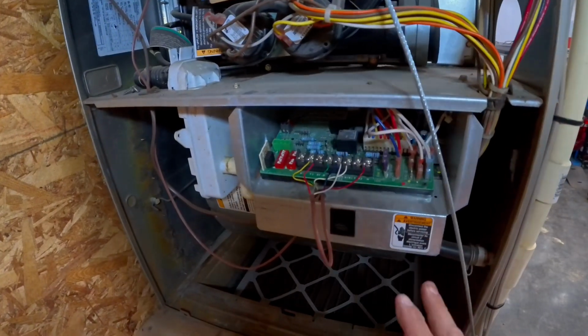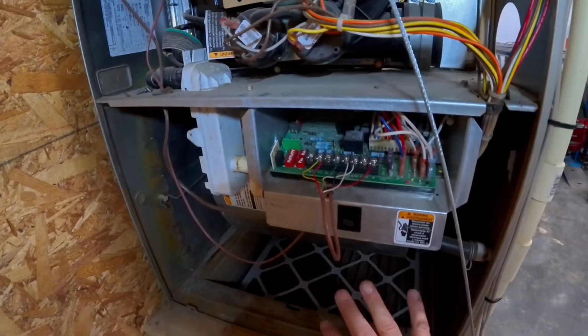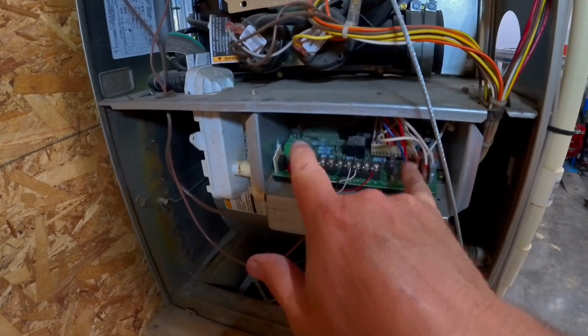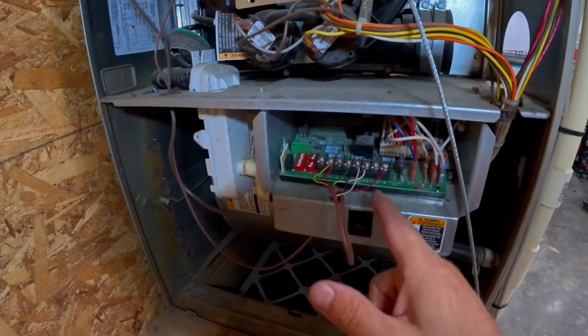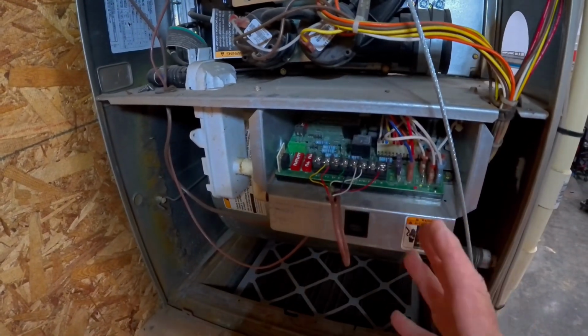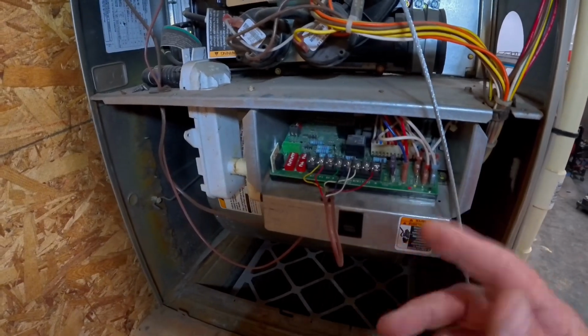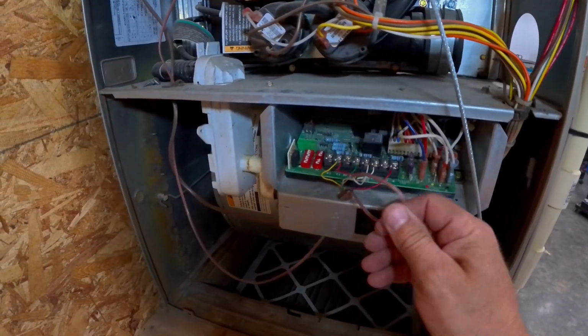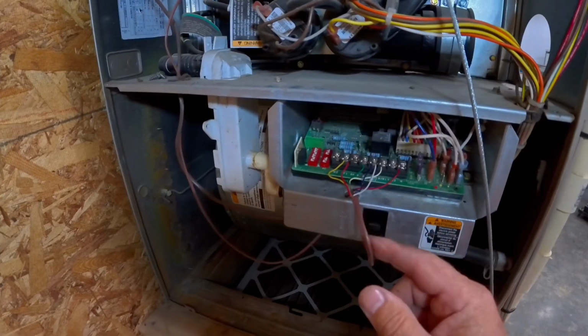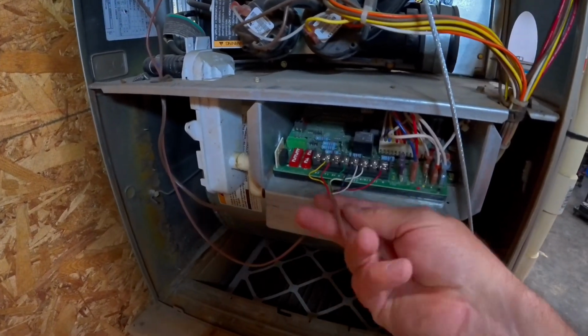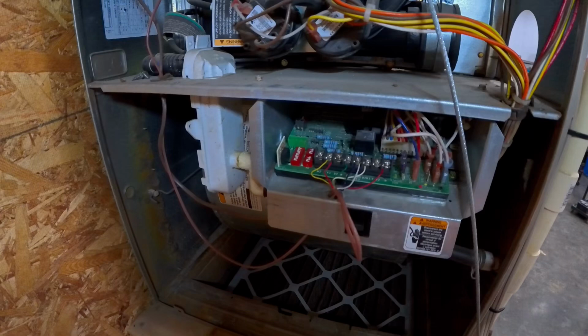Alright, so now we have our service panel removed, which is obviously giving us access to the blower and to the main board of the system. Right here on my system, and they're all fairly similar, but none of them are the same unless they're the same models, obviously, this here is our thermostat wiring. You got 2 wires usually. You got a 5-conductor wire and usually a 2-conductor wire. I'll explain those in a minute.